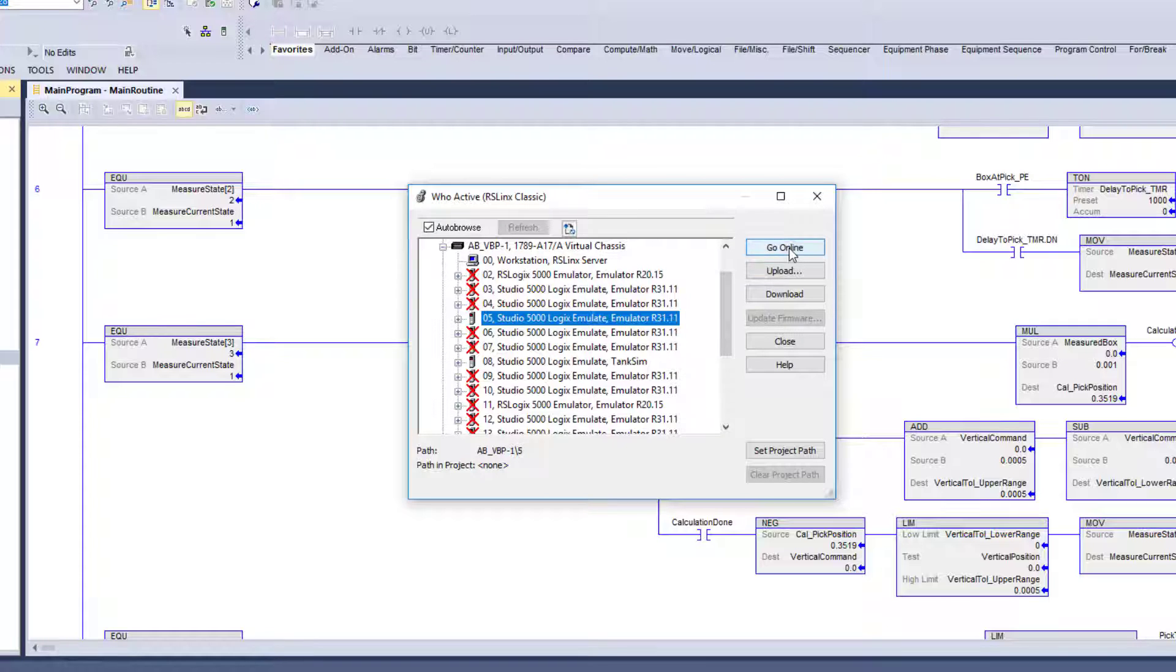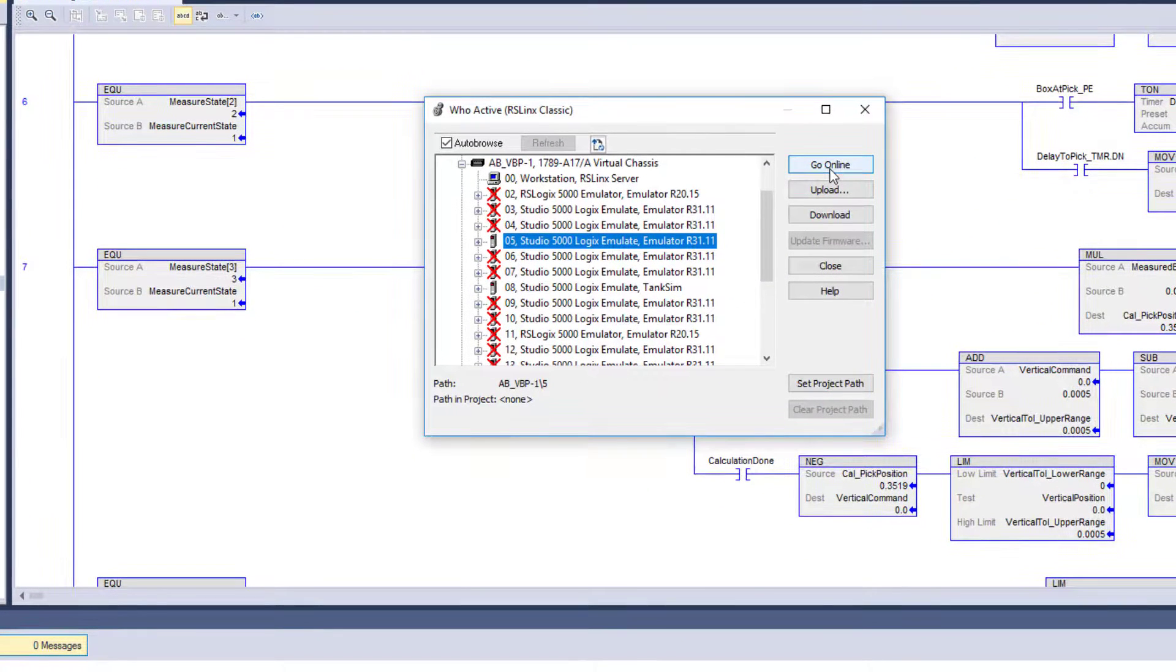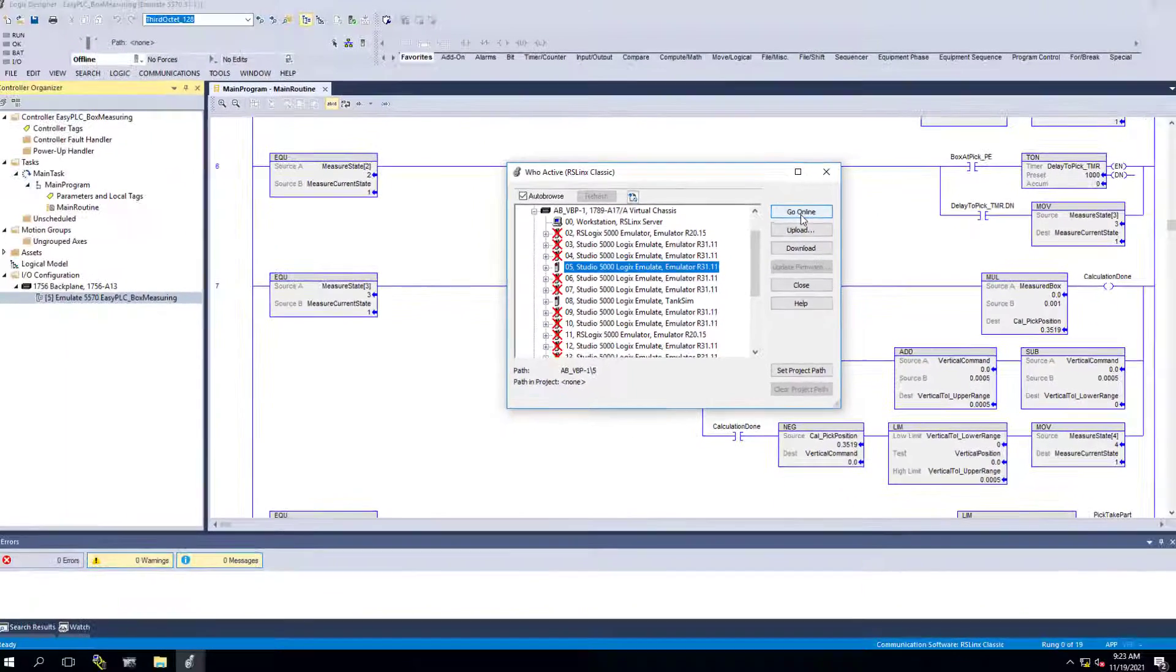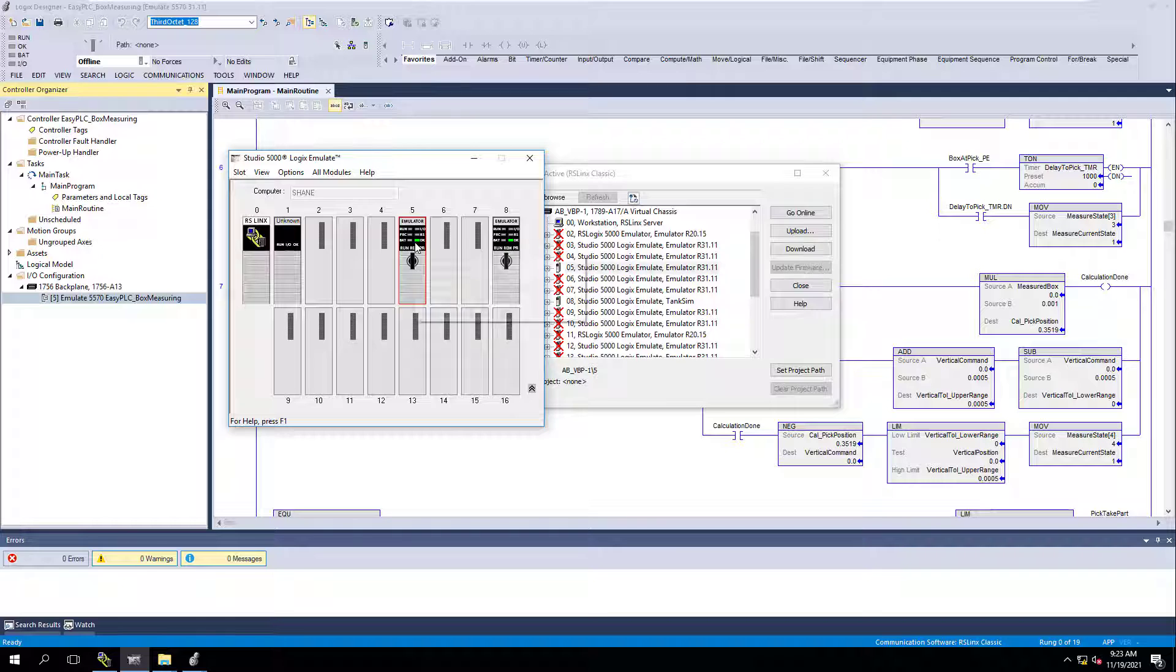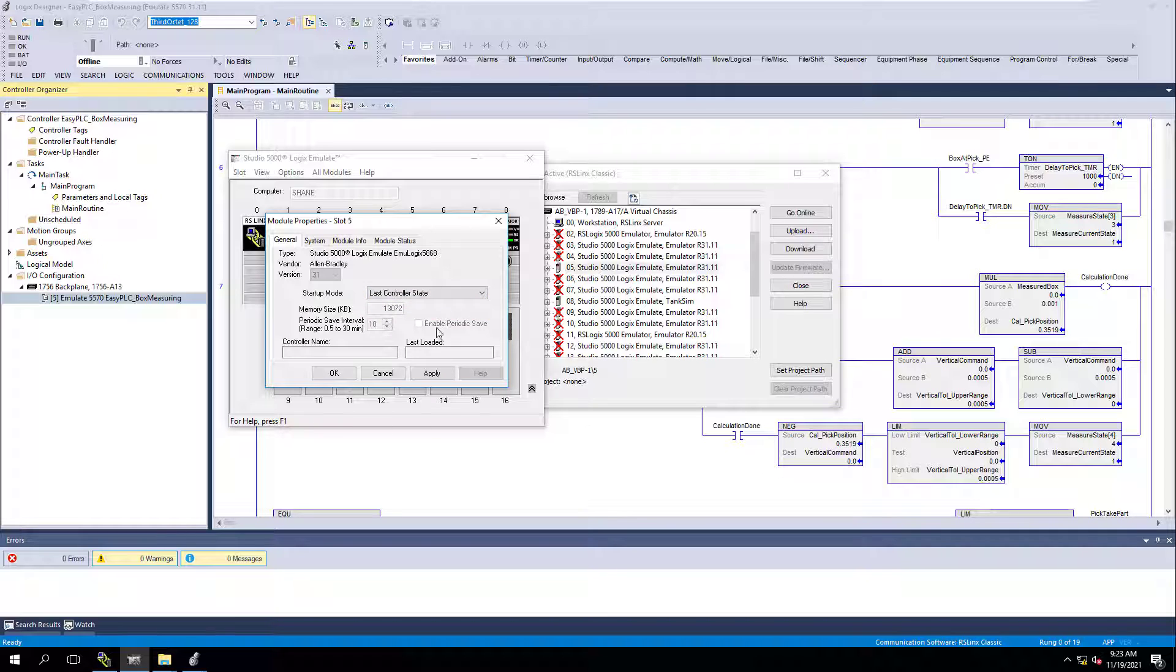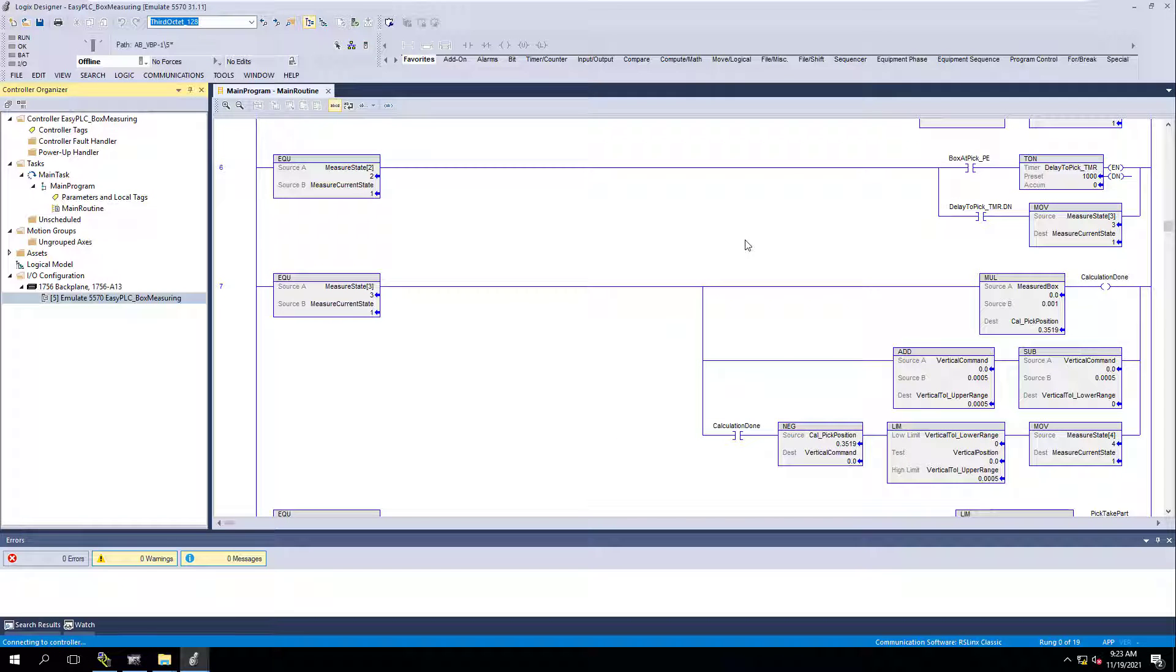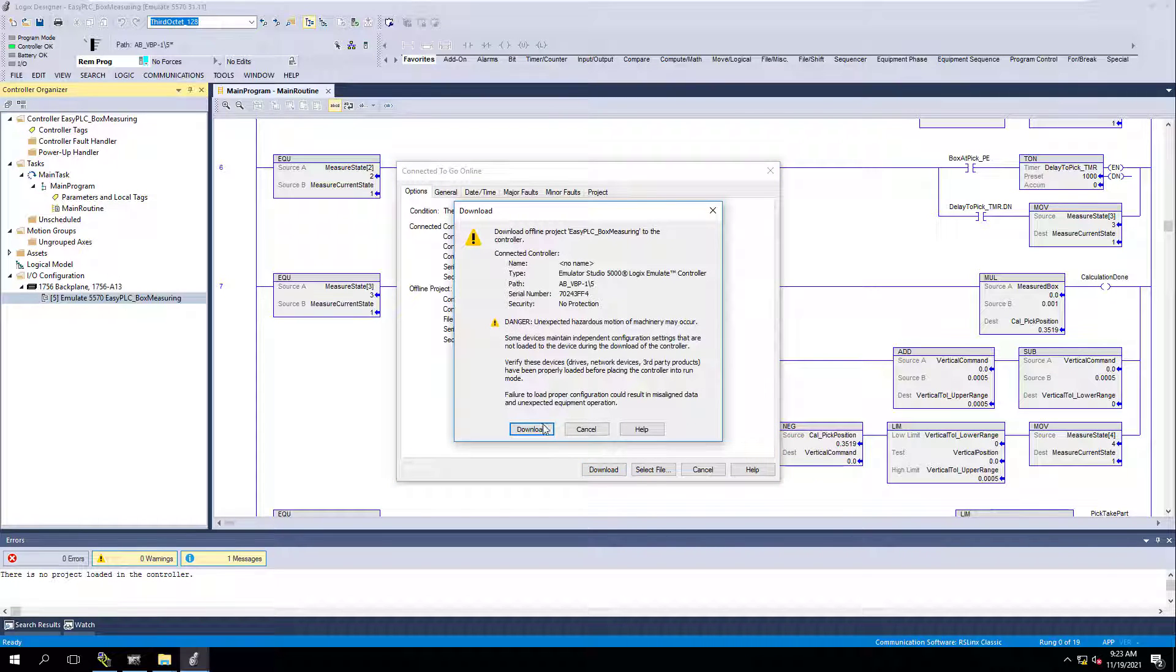Personally, what I like to do is I like to go online and then download. A lot of people have preferences to this and they would like to just go ahead and download. But there is sometimes an issue with emulation or stuff like that where your processor might get stuck depending upon your configuration or your processor. Let me show you this. Your processor configuration right here, if this is set in, the startup mode is in program or remote program, you're going to see that. I like to change this to last state. And then when I do that, I can actually come over here and go online.